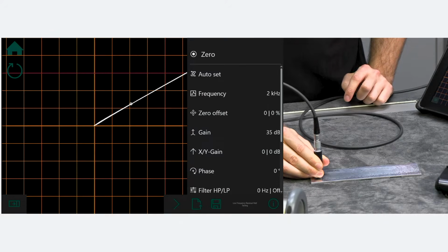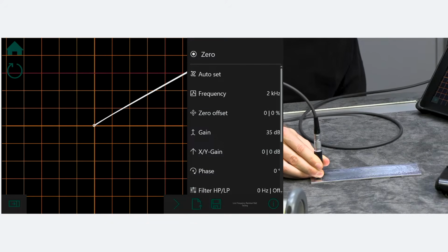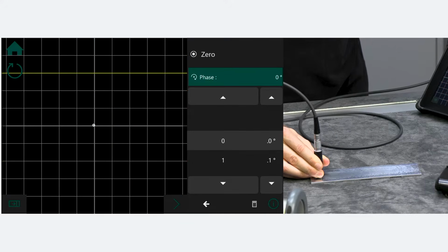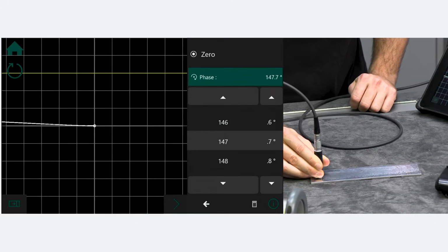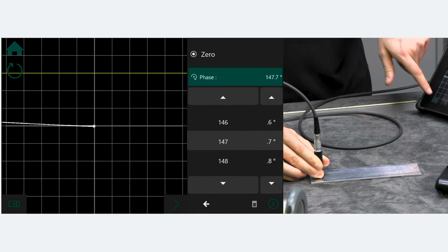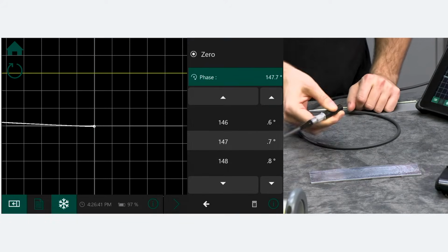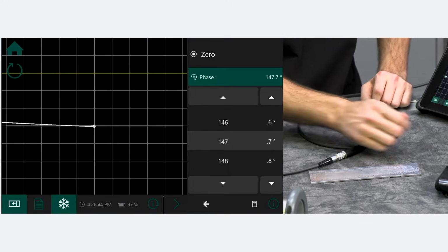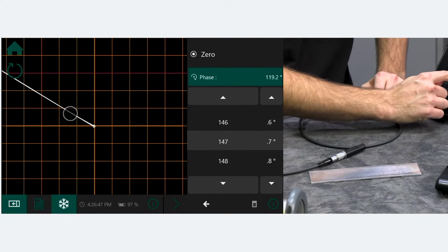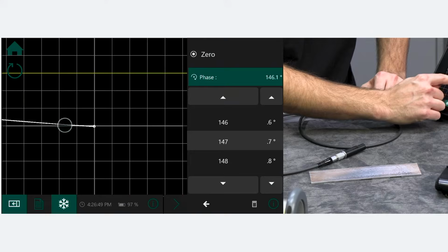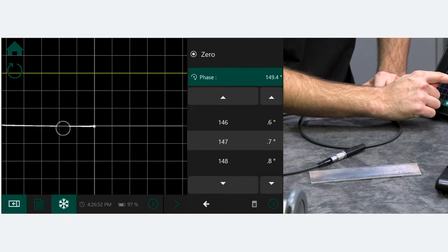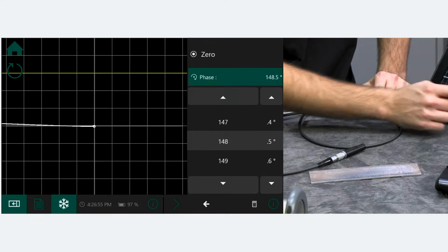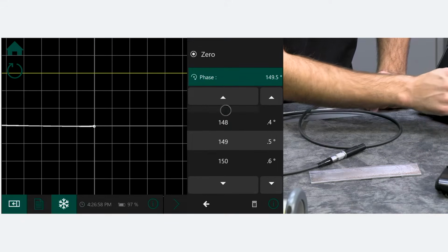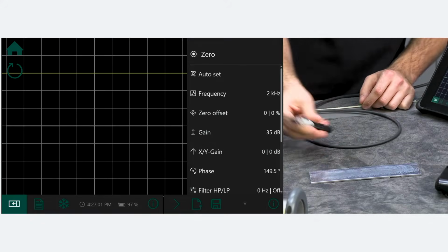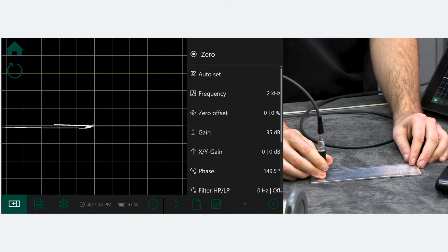And then we have now the liftoff effect if I'm moving the probe. And we can make this liftoff very fast in one direction. We press one time on phase, and it's directly moved in this direction. If we would like to move the phase manually, I can freeze the signal. So I move the probe and I freeze the signal. And now I can move the signal by touching it on the screen and doing that manually, or I can move it with the parameters directly here. Okay, and then we start with the testing.